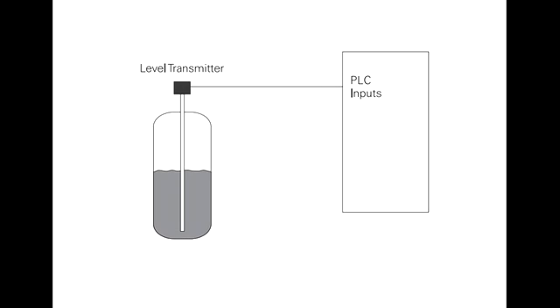Analog inputs. An analog input is an input signal that has a continuous signal. Typical analog inputs may vary from 0 to 20 milliamps, 4 to 20 milliamps, or 0 to 10 volts. In the following example, a level transmitter monitors the level of liquid in a tank. Depending on the level transmitter, the signal to the PLC can either increase or decrease as the level increases or decreases.